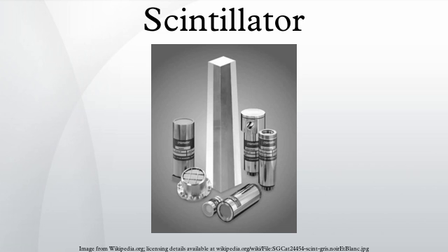The advantages of plastic scintillators include fairly high light output and a relatively quick signal, with a decay time of 4 nanoseconds, but perhaps the biggest advantage of plastic scintillators is their ability to be shaped, through the use of molds or other means, into almost any desired form with what is often a high degree of durability. Plastic scintillators are known to show light output saturation when the energy density is large.